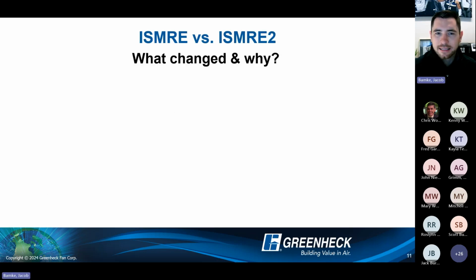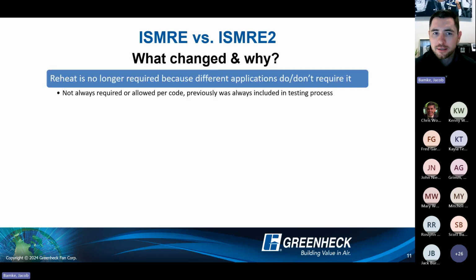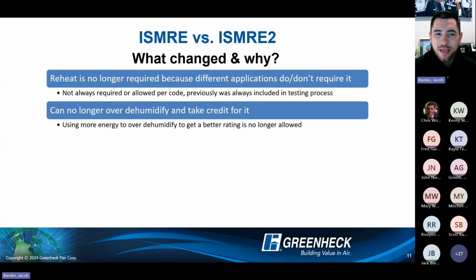You'll notice I said ISMRE2 on the last slide. So what changed before they really required this? They wanted to make sure that they fine-tuned some of the test procedures. So reheat is no longer required, because applications do or don't require it when you're using this type of system. You can't over dehumidify and take credit for it. So this is basically saying whatever you dehumidify to during your full capacity conditions, you can only take credit for moisture removed to that same leaving dew point, even at your part load conditions. This is just ensuring that you're using high efficiency components.